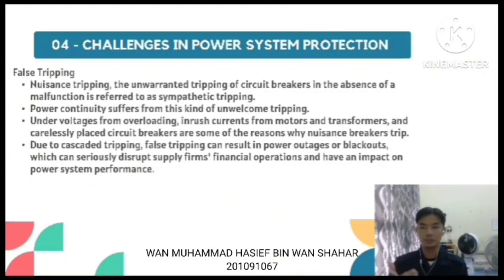Okay, secondly, false tripping. Nuisance tripping, the unwarranted tripping of a circuit breaker in the absence of a malfunction, is also referred to as sympathetic tripping. This kind of unwelcome tripping hurts power continuity. Undervoltage from overloading, inrush current from motors and transformers, and carelessly placed circuit breakers are some of the reasons for nuisance breaker trips. Due to cascaded tripping, false tripping can result in power outages or blackouts, which can seriously disrupt the supply firms' financial operation and have an impact on power system performance.